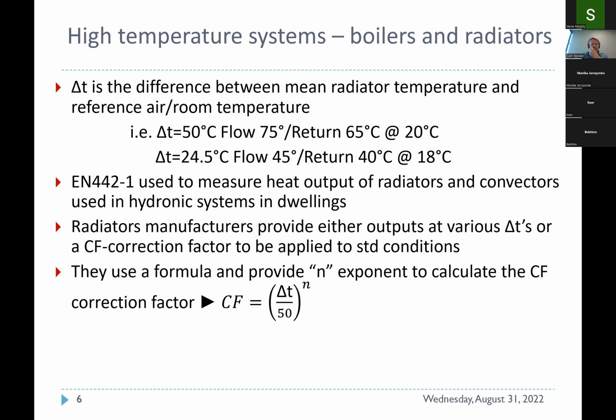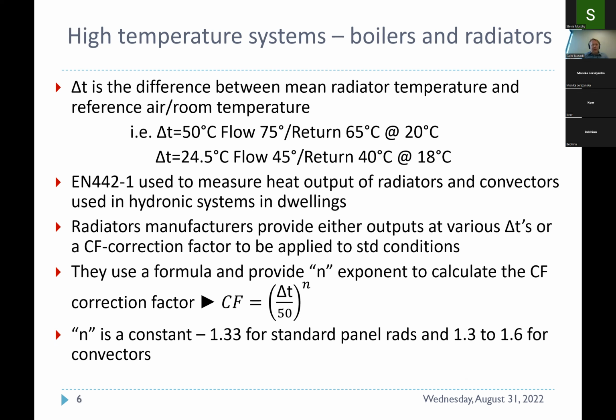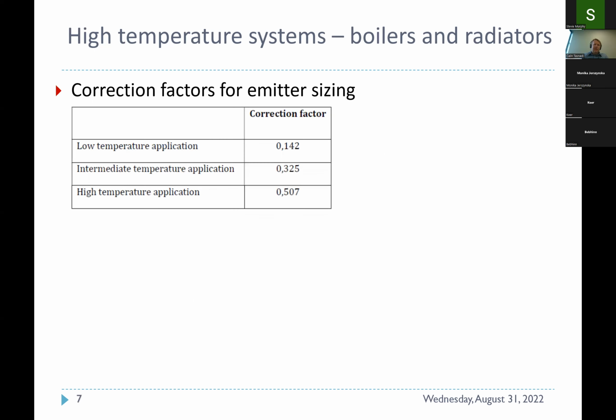Manufacturers provide what is called an exponent, n, and then we use a formula. The correction factor is calculated as the delta T at which we want to find the new output, divided by the delta T at the standard, delta T 50, all to the power of n. That's basically how this is calculated. This is a constant, and it is typically 1.33 for standard panel rads and varies from 1.3 to 1.6 for convectors. Correction factors for emitter sizing, depending on the type of application, vary, as mentioned earlier, from 0.14 to 0.5. So the higher the temperature, the bigger the correction factor will be.